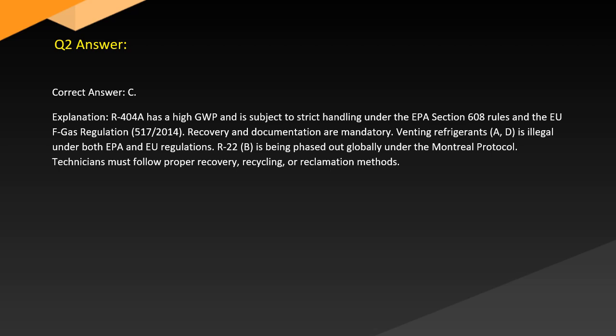Answer. Correct answer: C. Explanation. R404 is subject to strict handling under the EPA Section 608 rules and the EU F-Gas Regulation 517/2014. Recovery and documentation are mandatory. Venting refrigerants, A and D, is illegal under both EPA and EU regulations. R22, B, is being phased out globally under the Montreal Protocol. Technicians must follow proper recovery, recycling, or reclamation methods.